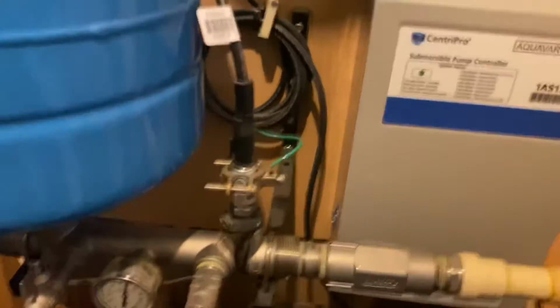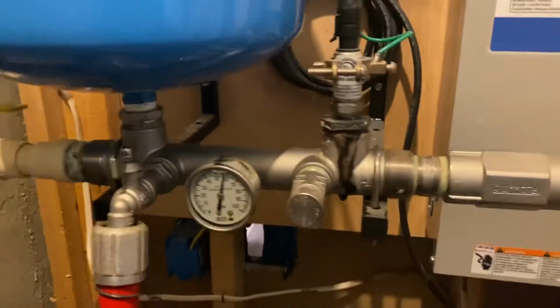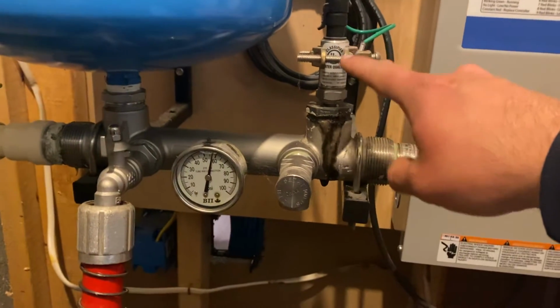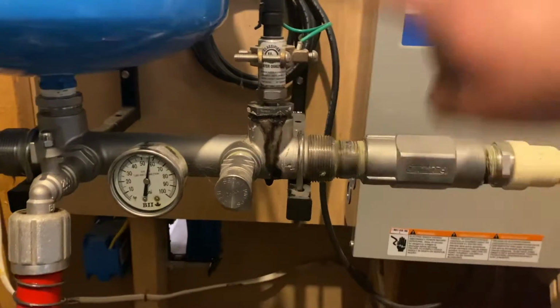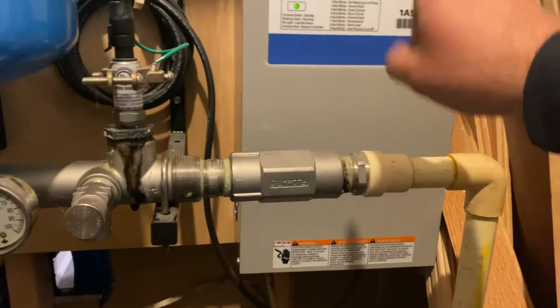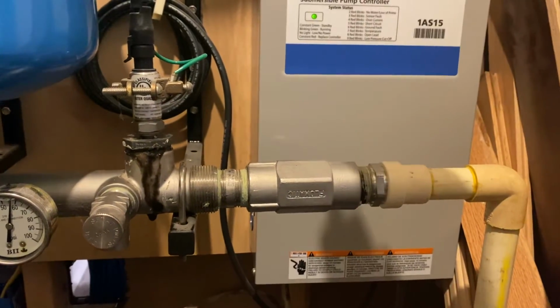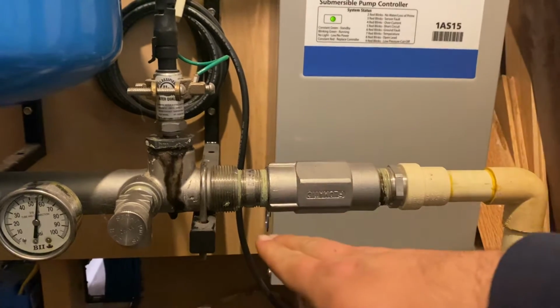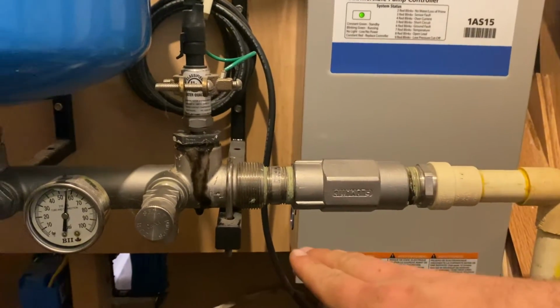How this system works: you have this little guy right here, which is the transducer. It reads the pressure in the pipe and talks to the computer over here, which raises or slows down the speed of the pump depending on how much water is being called for.